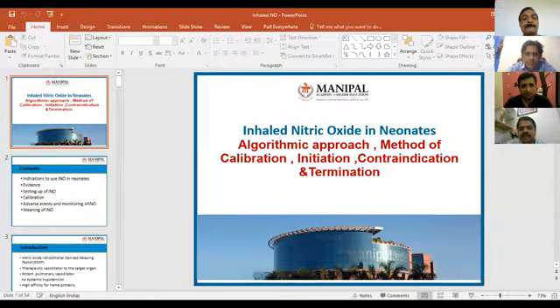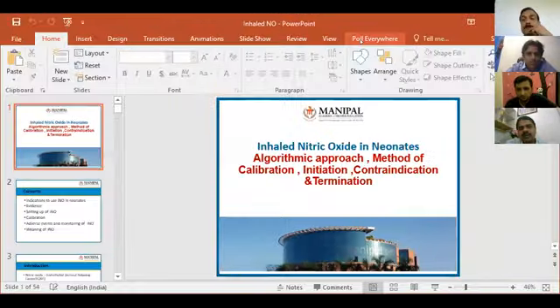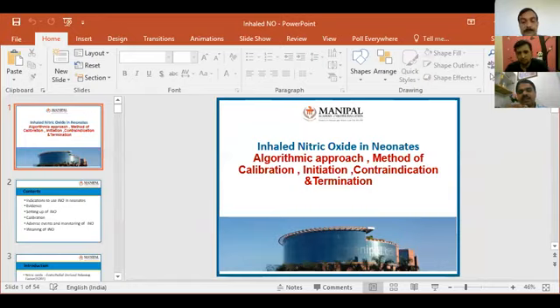Yeah, go ahead, please. See, regarding wiggling, this is only at the beginning, once you want to start. So you will start with wiggling. The optimal wiggling in neonates is generally considered to be up to the umbilicus. In the pediatric age group, up to the lower abdomen, and in adults, if they are on high frequency, up to the thigh. But in neonates it is up to the umbilicus. Sometimes, after giving surfactant, once the compliance increases, the wiggling can suddenly increase and the tidal volumes can increase. At that time, you have to sit at the bedside and tell the nurse, if the wiggling is more, you need to come down on the amplitude or delta P.